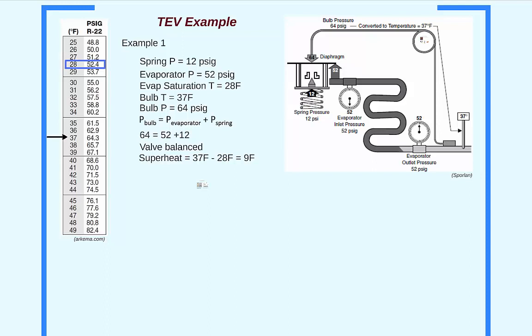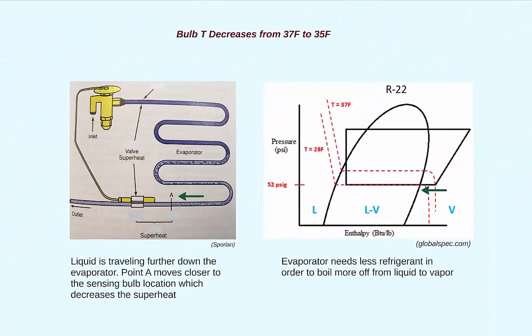What would happen if the outlet temperature decreased from 37 degrees Fahrenheit to 35 degrees Fahrenheit? To start, let's remind ourselves how the cycle should respond if a change in cooling load causes the superheat to decrease. When the cycle's superheat decreases, liquid refrigerant is traveling further in the evaporator. Point A is now moving closer to the sensing bulb.